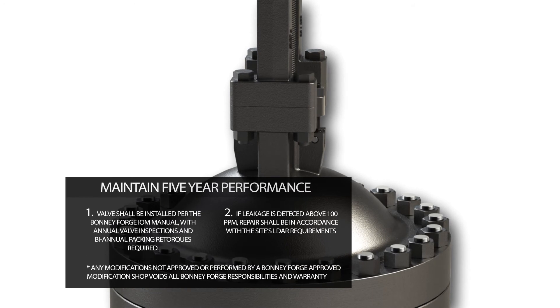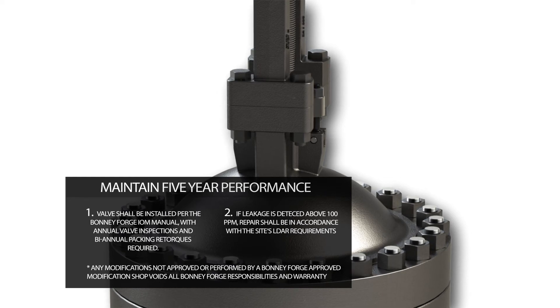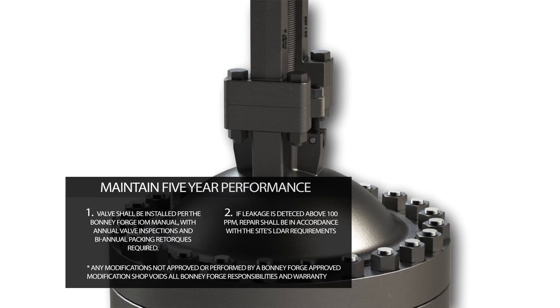In order to maintain the Bonney Forge 5-year performance, the valve shall be installed per the Bonney Forge IOM manual, with annual valve inspections and biannual packing retorques required. If leakage is detected above 100 ppm, repair shall be in accordance with the site's LDAR requirements.